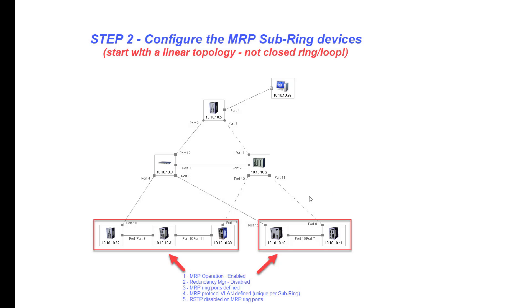The next thing we're going to do is go into the MRP subring switches. For all of these switches, we're going to enable the MRP operation, make sure that the redundancy manager is disabled, define our ring ports, and also define a unique VLAN ID for the MRP protocol. This is not for the data traversing the network — it is just for the MRP watchdog packets that get sent out to verify and test the integrity of those rings.